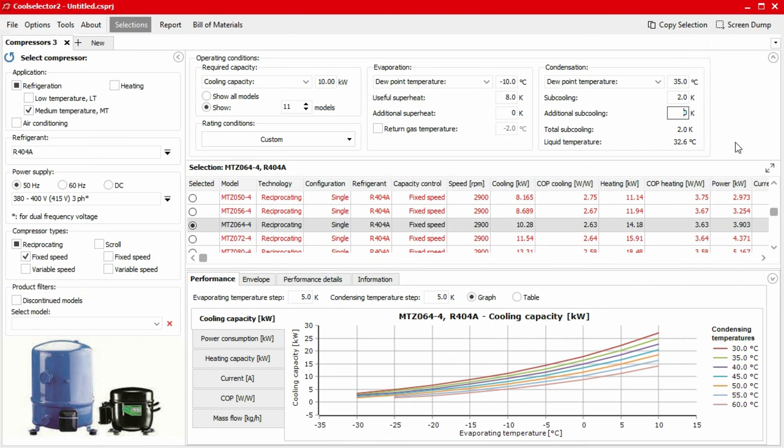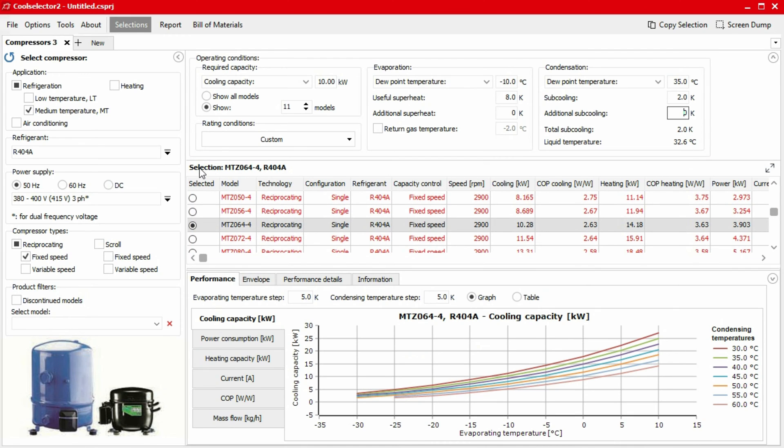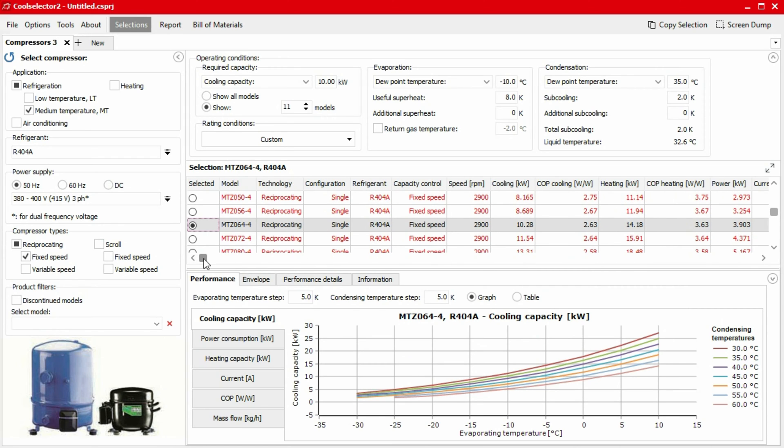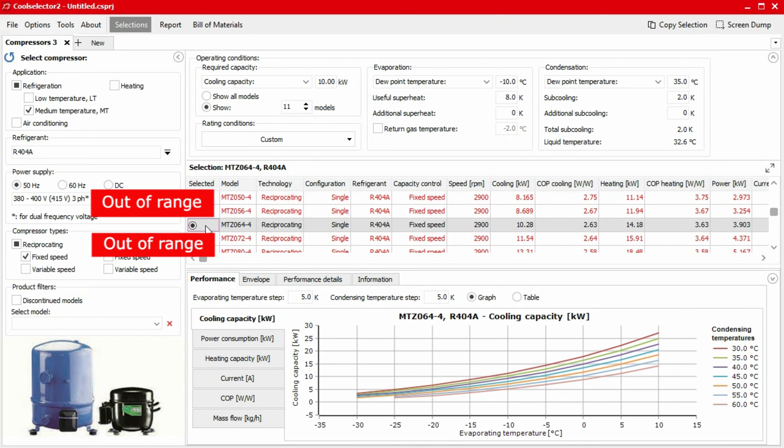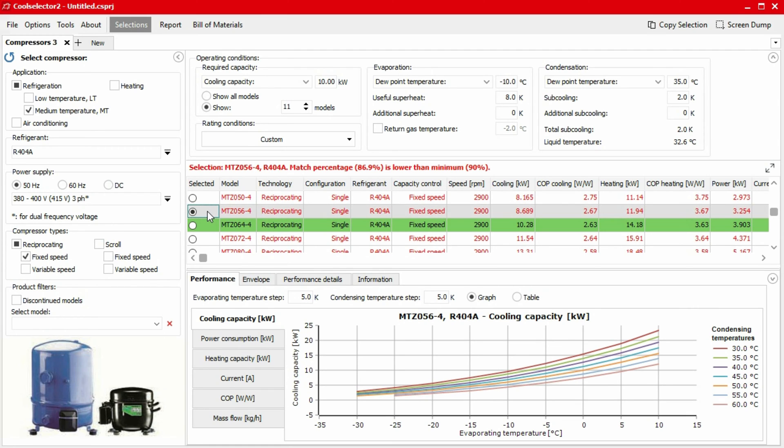The selection table now lists the compressors which are most applicable to your system definitions and requirements. On the last column, we can find how closely each compressor matches the defined capacity. It's important to note that when a compressor's capacity is out of the minimum and maximum range, CoolSelector 2 shows a warning and changes the list entry text color to red. The range is set from 90% to 110% match by default, but you can change this in the preferences. The best matching compressor, according to capacity, will be highlighted in green as you can see.